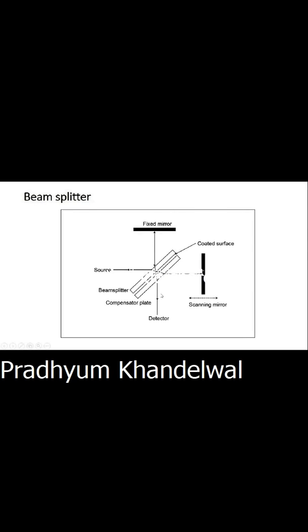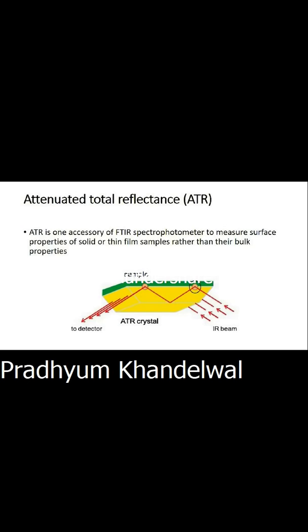This is a beam splitter, as seen in the Michelson interferometer — here is a close look at how it looks. Now we are talking about Attenuated Total Reflectance (ATR). It is an accessory of the FTIR spectrometer used to measure the surface properties of solid or thin film samples rather than bulk properties.